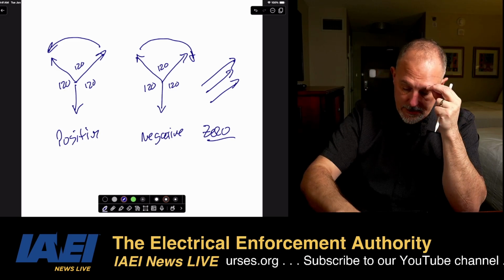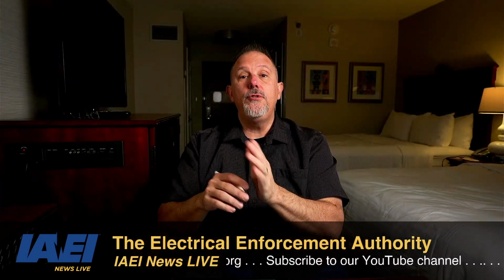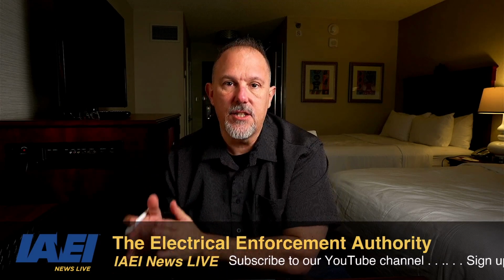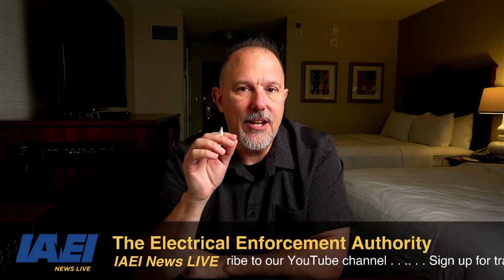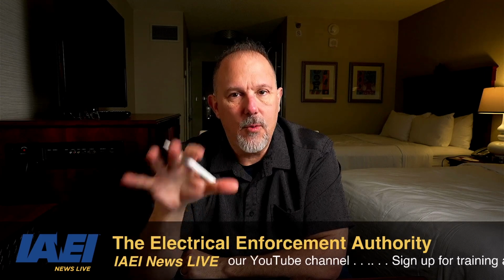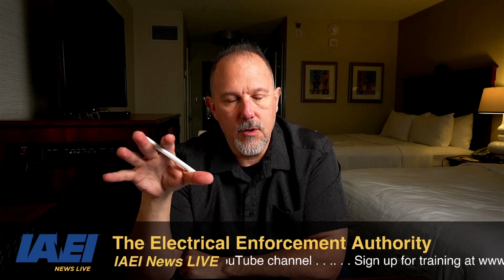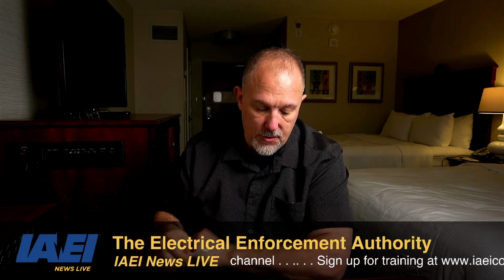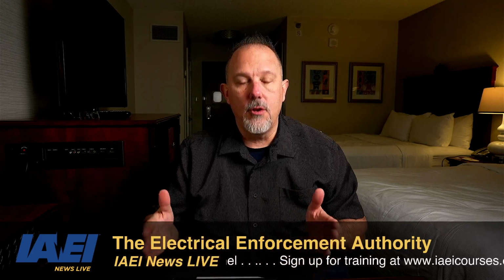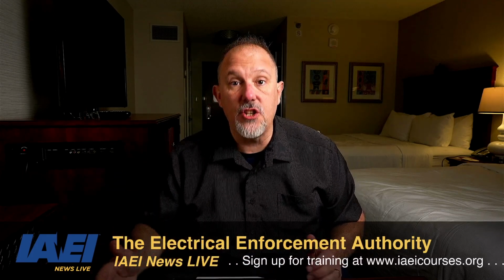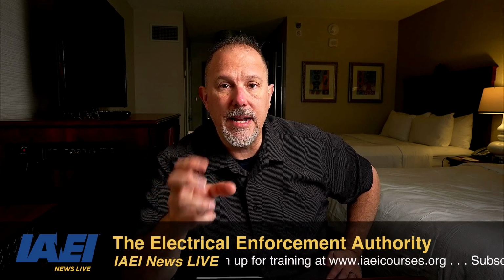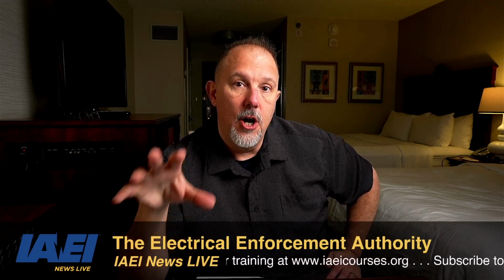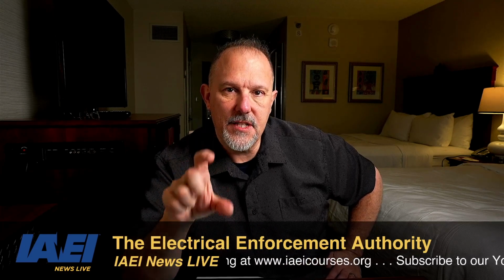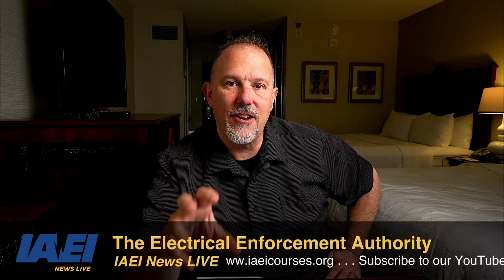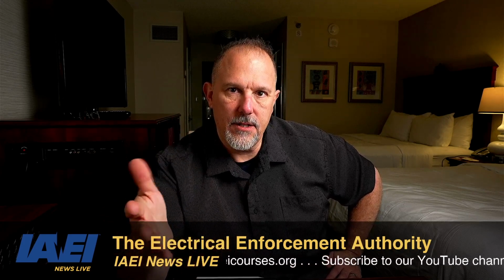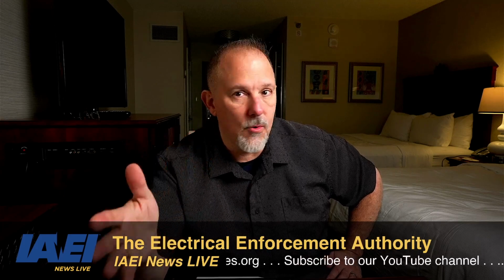Probably TMI, but in any case, we use the zero sequence impedance model to calculate ground fault currents. And that's why that information is required to be on the nameplate. If you are into power systems analysis and you are looking at protecting generators, you need to know what the negative sequence currents are. You might need to put negative sequence relays on that generator because negative sequence currents in a generator generate heat, like eddy currents. They will generate heat, and that can destroy a generator.